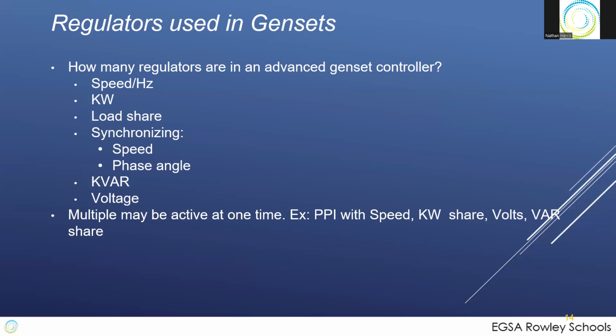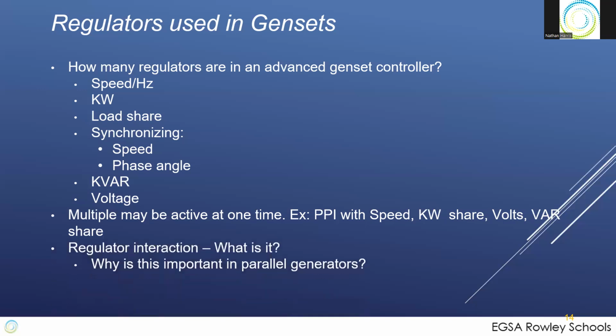And then having two generators feeding a single load, you get into this regulator interaction. This is really important in parallel generation, so you don't fight each other. I like to use the example when I'm driving down the road and the wife's next to me. I'm driving, and she's going, "You're going too fast. You're going too fast." Well, there's two of us regulating one quantity. I've got the control, but she can be in my ear telling me to slow down, and that is two regulators interacting with each other, and this interaction can cause resonance as well. So be careful of regulator interaction between regulators in the same system or regulators in parallel gensets, for example.